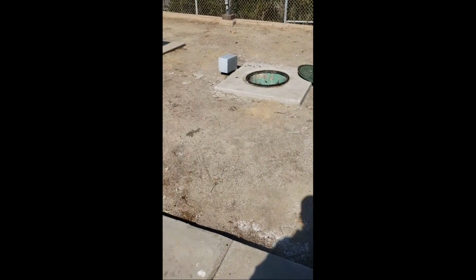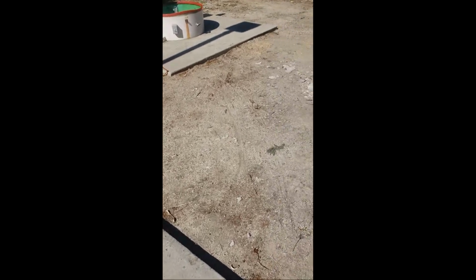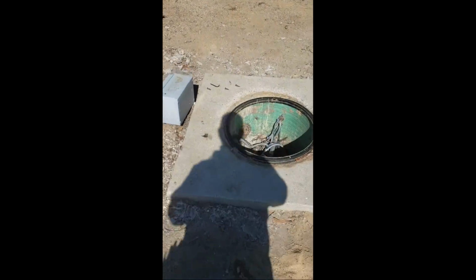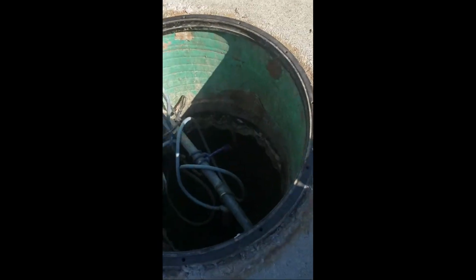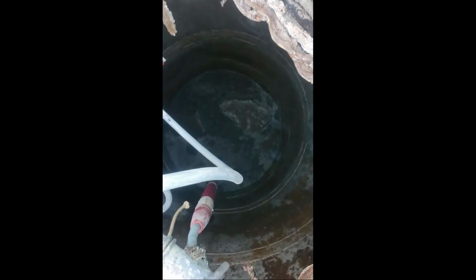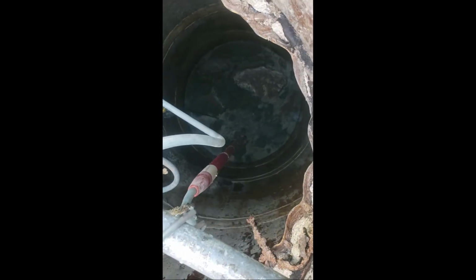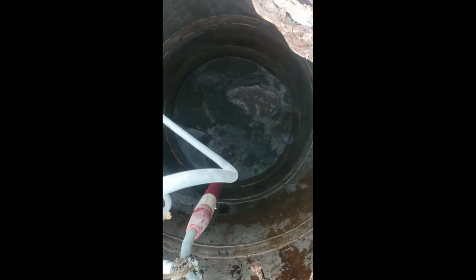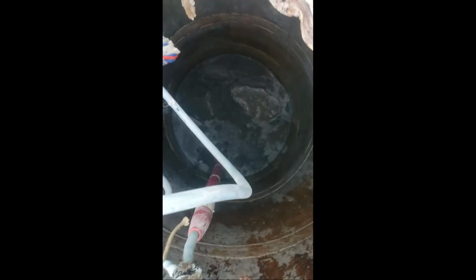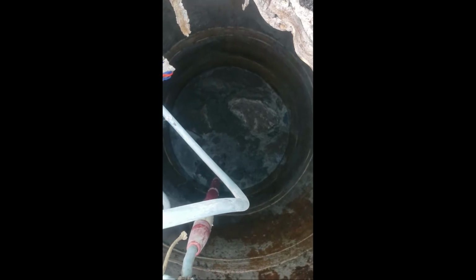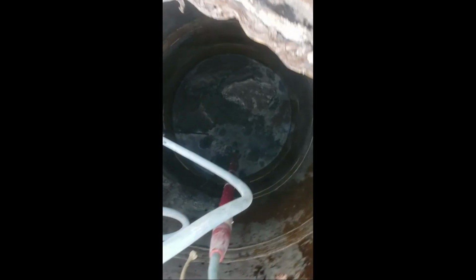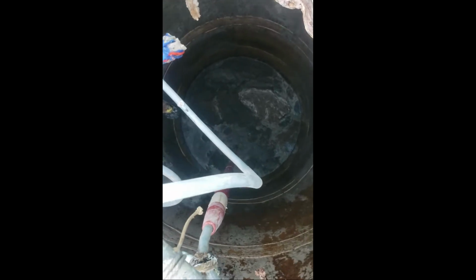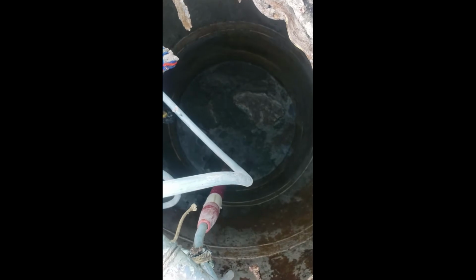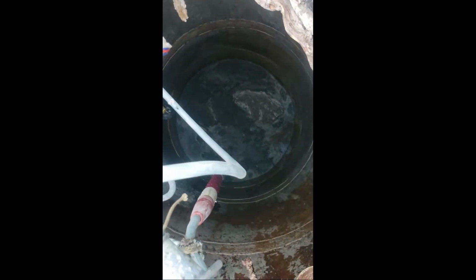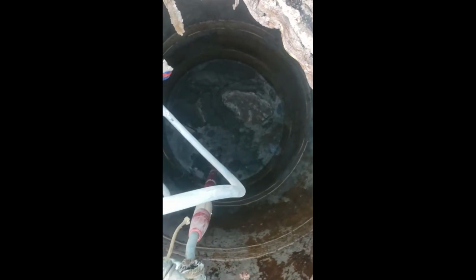So here we have the two major components of a pump station, the wet well and the dry well. Everything gets pumped into the wet well. I hope you guys are appreciative - I'm risking my phone for this. This is the wet well here. What you see is a probe going down, sensing the level. This was just broken up, the solids, but what you're seeing on top are the fats, oils, and grease accumulating. We have to go through and periodically break those up - we don't want those coagulating and getting on the walls or getting too big. Sometimes we have to net those out.